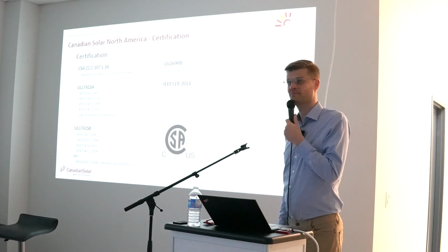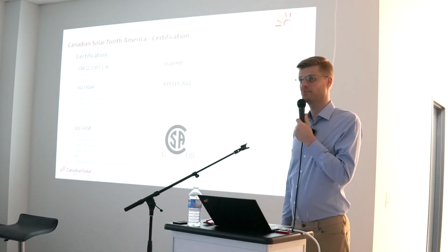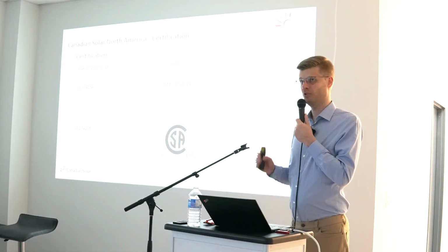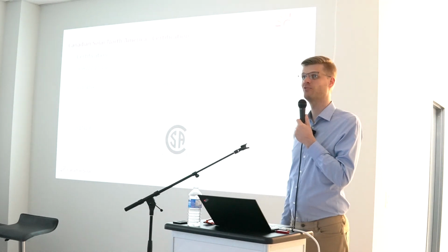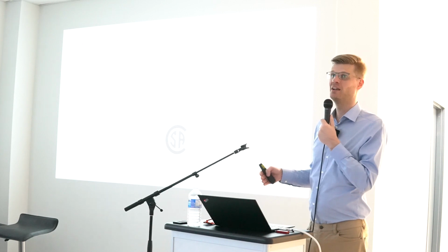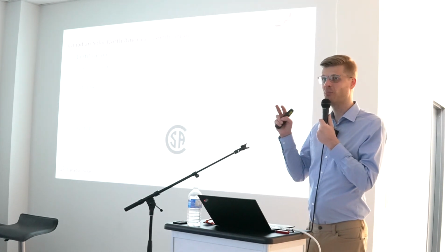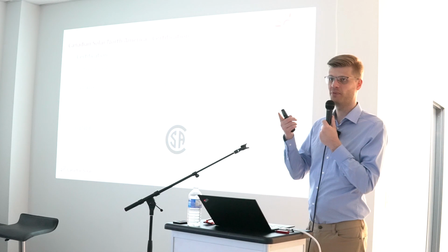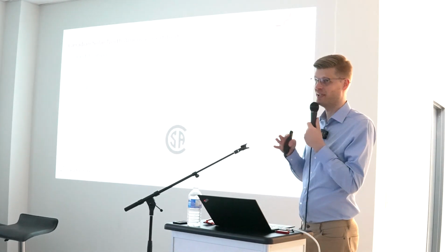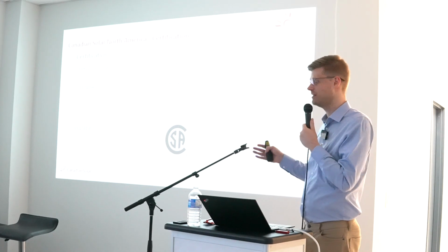Art, a question for you on code in Canada, 1500 volt. Is that any rooftop, or is it not? Any commercial rooftop. If it's a residential dwelling, the voltage is limited to 600 volts. So you're fully correct. If you have a regular residential rooftop, then you're definitely capped at 600 volts, the same as the US. Once it is commercial, then you can go all the way to 1500. Any commercial. There are some critical buildings or critical infrastructure, like I think schools have some limitations in some jurisdictions, not in others. Hospitals sometimes go under these critical infrastructure rules, but it's not a rule; it really depends on the inspector and the plan review.